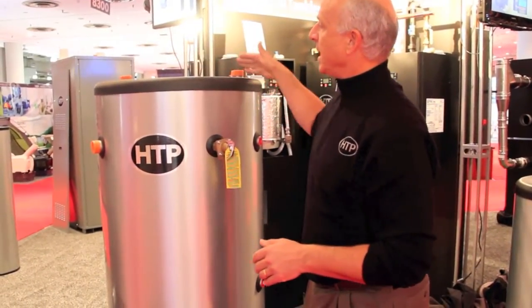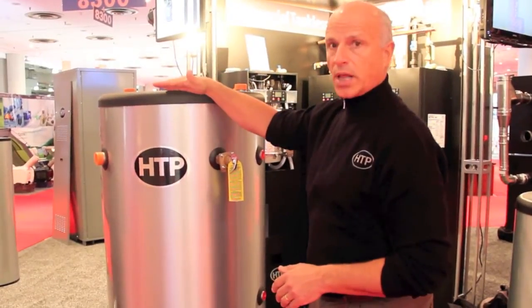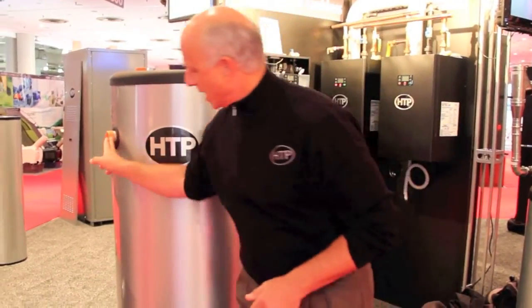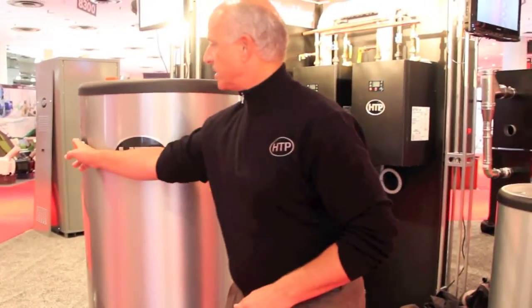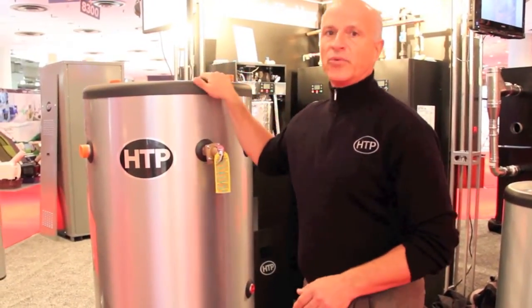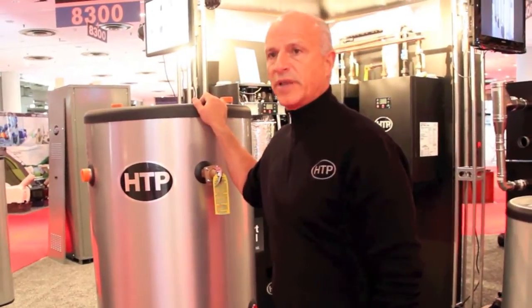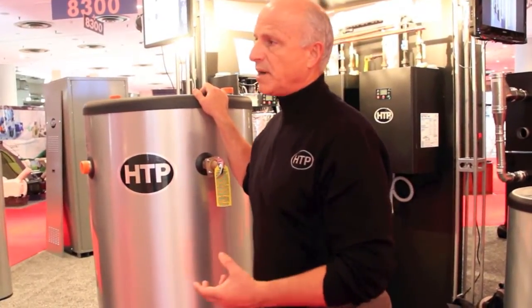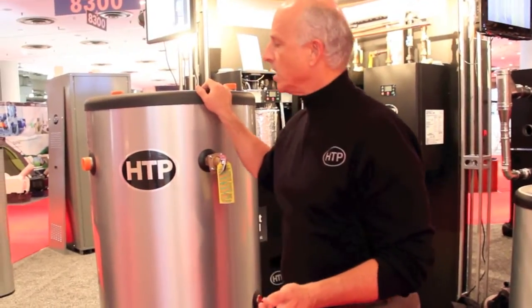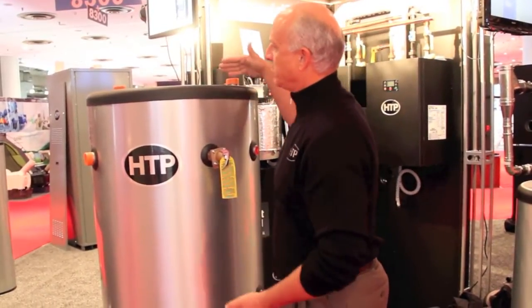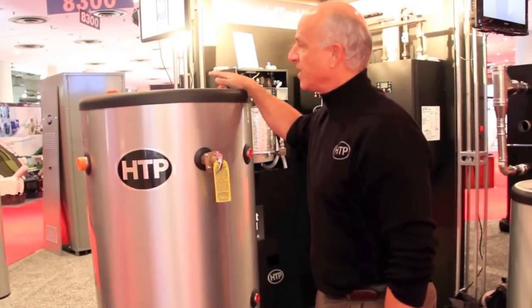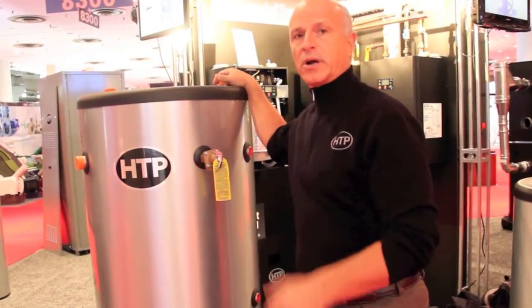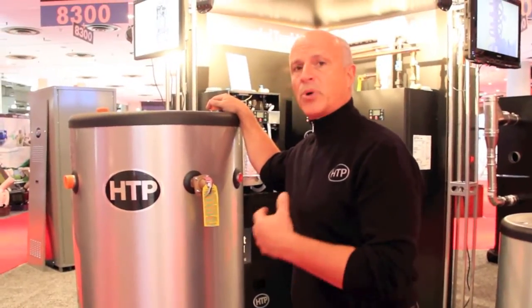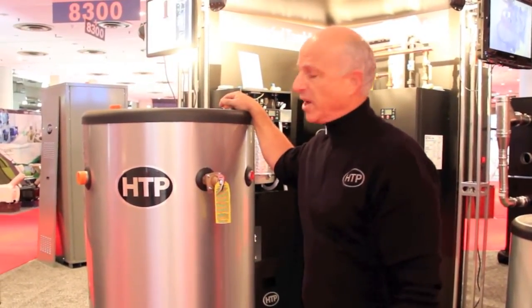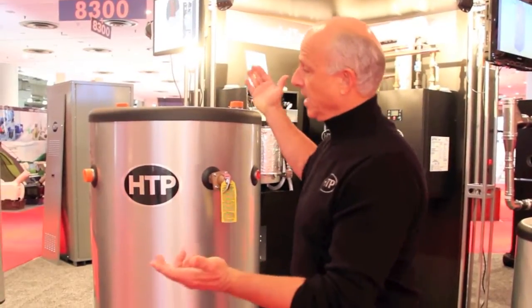So not only do we put the tappings on the top and lower the overall height, but we also put tappings on the side. So now we have tappings both on the side and on the top. And that really is a nice feature for customers. They've come back to us and said, we have a lot of problems sometimes putting the unit in difficult areas, and by getting the size down, and by having the ability to plumb this up off of the top of the unit, it will really enhance our ability to put our products in areas that we couldn't go before by just having the side tappings. And if the customers do need to come out of the side, we've got it also.